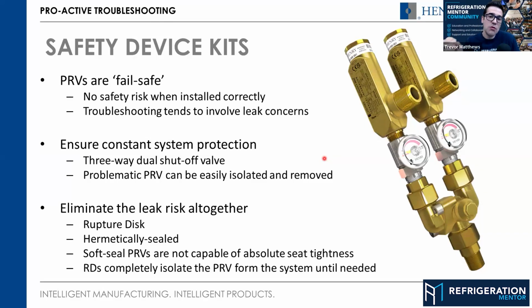That's perfect. So if I have a relief on this example, we've got the three-way valve, we've got the rupture disc, we've got the spring. You said if the rupture disc goes, it's a one-shot deal, right? So that opens up. But if that spring opens up and then it seats back down, can I reuse that one that opened, or do you recommend replacing that one? We always recommend replacing them.